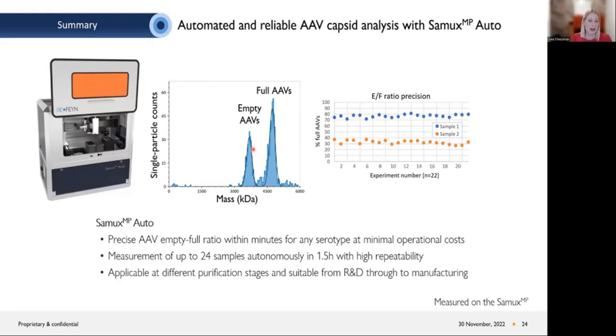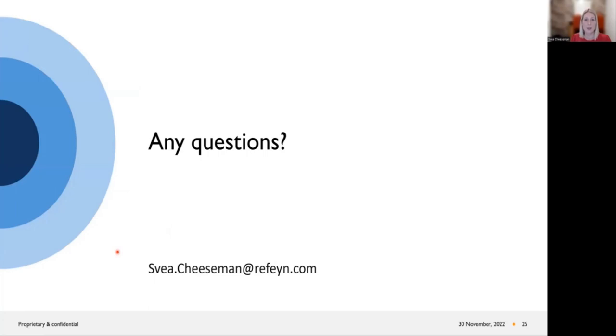In summary, the SamuxMP Auto delivers precise AAV empty/full ratios within minutes for any serotype at minimal operational costs. It can measure up to 24 samples autonomously in approximately one and a half hours with high repeatability. The SamuxMP Auto can be applied at different purification stages and is suitable from R&D all the way through to manufacturing. Thank you for your attention. I'm happy to receive your questions — please write to svea.cheesman@refine.com.